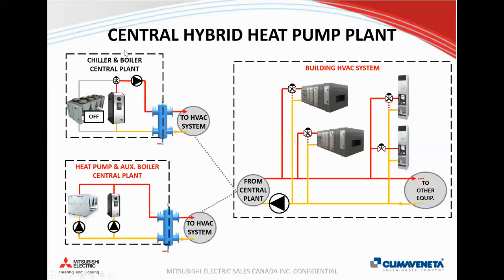So typically, if we have a chiller-boiler central plant with an air-to-water heat pump, if such a machine exists that can produce hot water or chilled water, it sounds great in theory to, instead of using a traditional chiller, use a reversible chiller that can operate in heating mode and use that in parallel with an auxiliary boiler. So whenever you can run off the heat pump, you supply hot water from the heat pump, and whenever it's too cold or perhaps you're not getting the efficiency that you want from the heat pump, you'll simply switch over to an auxiliary heat source like a gas boiler.